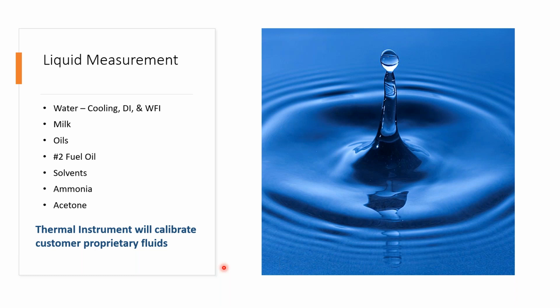Yes, typically we do, because of where our sensors are positioned, whether it's an inline unit or an insertion probe. If you've got a liquid measurement that you're doing and it's not always full, and it doesn't touch the sensor, if you've only got half a pipe and maybe it's just below that sensor point, well, the sensor is going to tell you no, you don't have any flow. Whereas if it's just below, you are really having flow. You're just not going to see it on the instrument. So it's best to position the instrument.